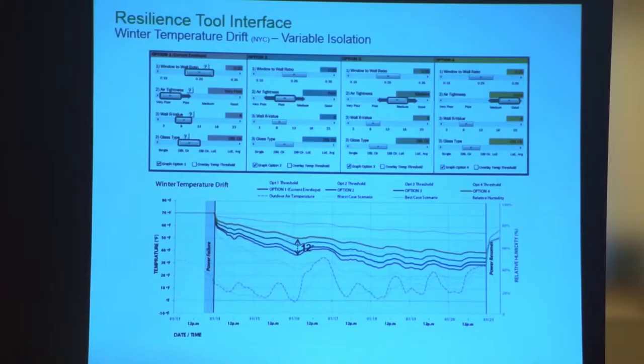It kind of leads on to this. This is the same climate, an apartment in New York. Here we've isolated, we've kept these parameters fixed: the 25 percent window-to-wall ratio, the R value, and the glazing type, but we're just adjusting the air tightness.